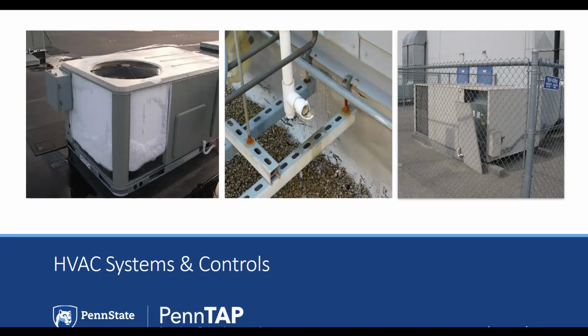In the photos, you can see the seized HVAC. This was due to faulty controls. You can see the broken P-trap, and you can also see the maintenance left incomplete in the right-hand photo. Although the doors on an HVAC can be meticulous to undo and then reinstall each time, making sure that the doors are secure means that debris will be blocked from getting in, as well as various animals. You can't guarantee the equipment is operating the same way as you left it after leaving it exposed long-term.